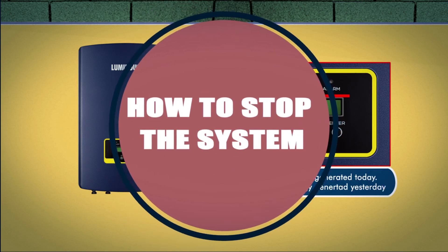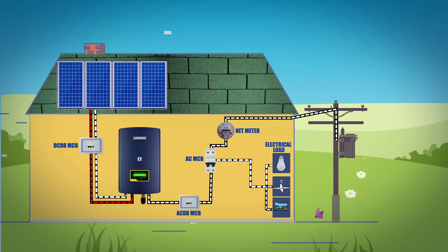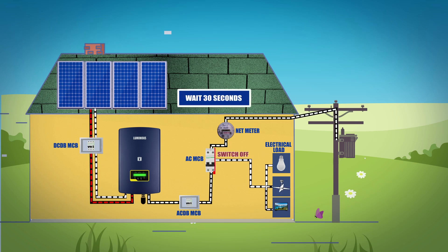To stop the inverter, the following steps must be strictly followed. Switch off the main supply. Wait 30 seconds. Switch off the DC MCB. All the LEDs of the inverter will be OFF in a minute.